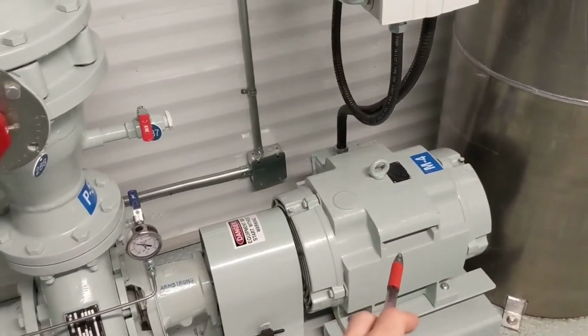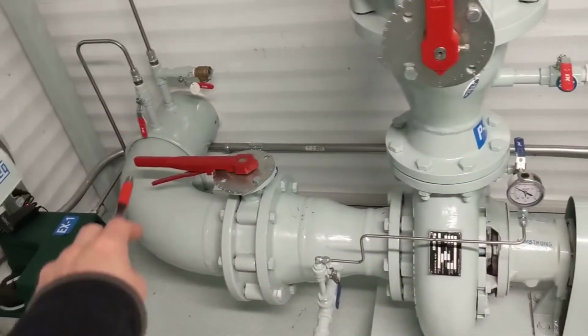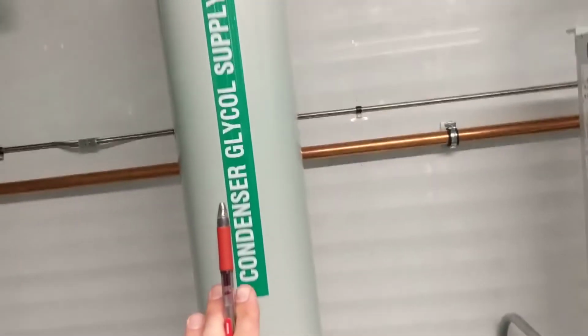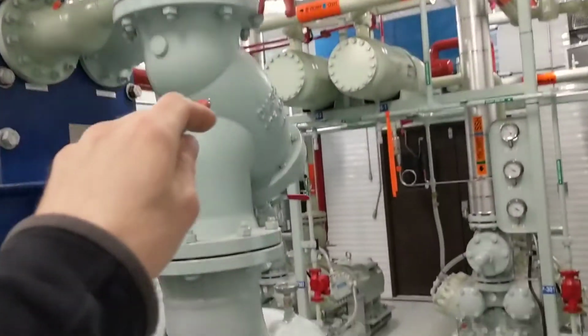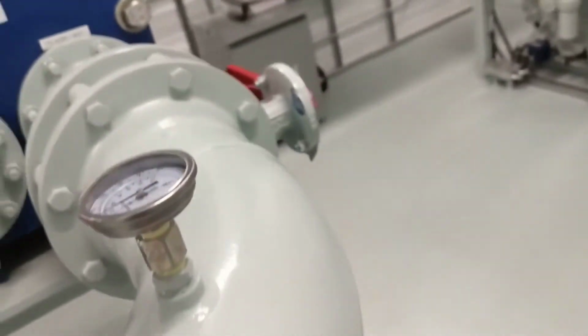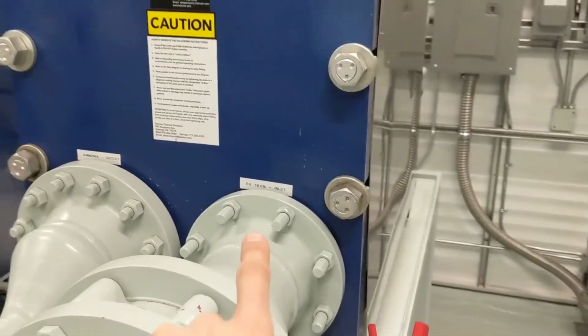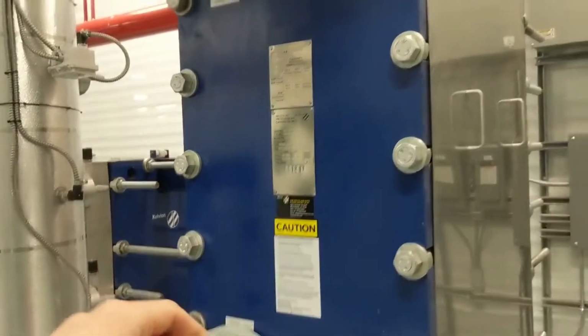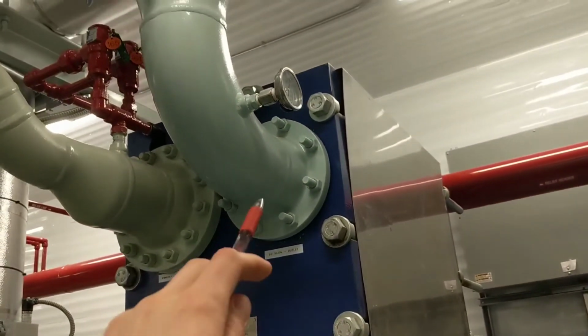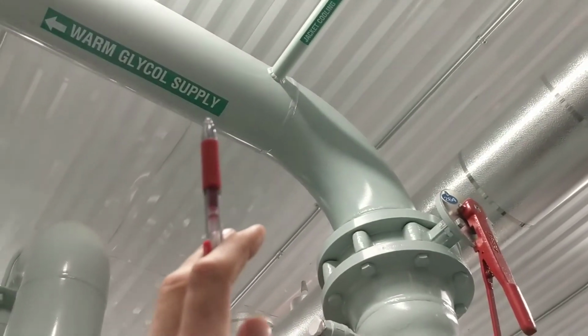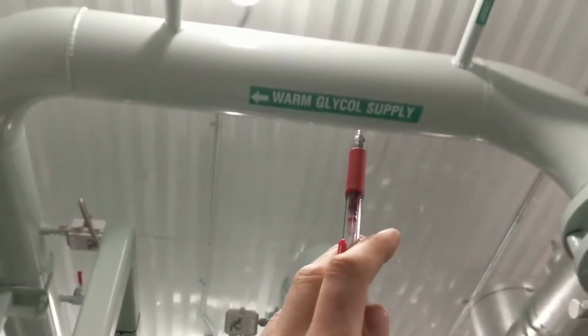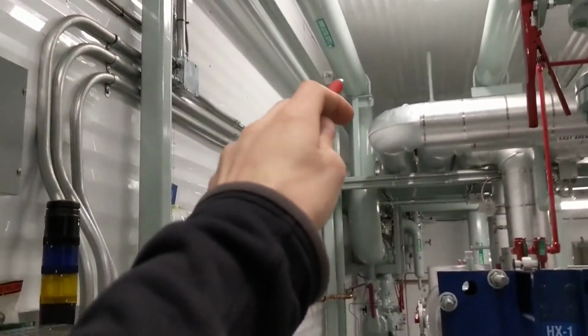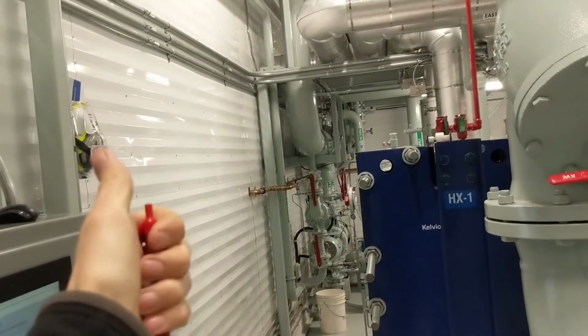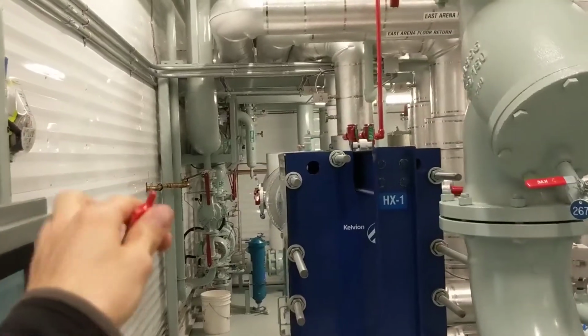So this is the glycol pump. That's the pressure. It's flowing this way, pushing the glycol this way, and then it's running up and over, and it's coming along here, and then this glycol is coming down through this strainer around here. You can see the temperature that it's going in to the inlet of the ammonia heat exchanger. It's picking up the heat from the ammonia as it condenses the ammonia, and then it's coming out here warmer than it was. This warm glycol is then flowing over there to where we just were, and it's giving up its heat to the snowmelt pit, the heat floor, or the warm floors for the arenas, and then it's flowing outside.